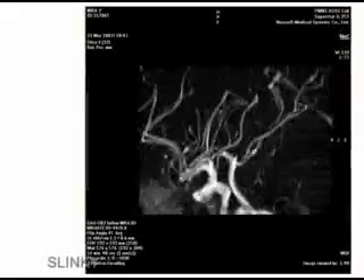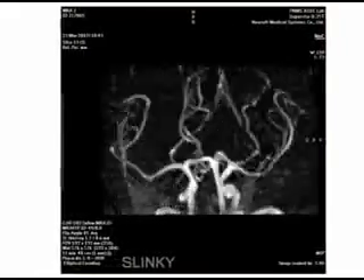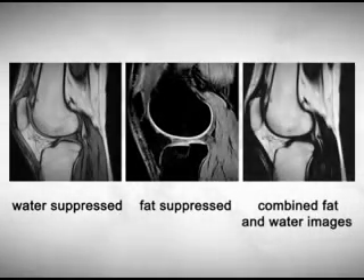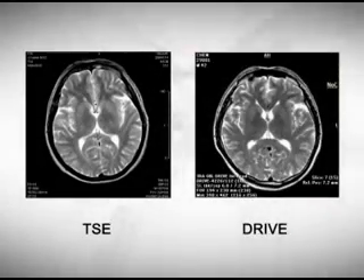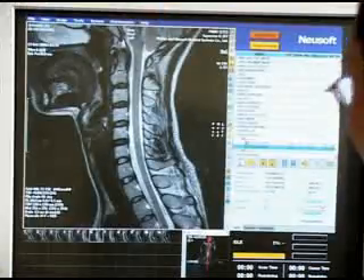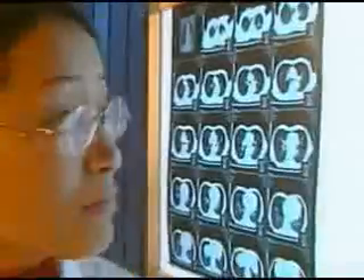The Superstar's acquisition method in MRA 3D is called Slinky, a technique that can improve the continuity of vessels. Through single scanning, water-fat separated imaging technology achieves three types of images. DRIVE can observably increase SNR especially in cerebrospinal and other body liquids. This sequence is useful for small apparatus imaging targets such as the inner ear, eye, and some brain details. The DRIVE sequence is also able to reduce the TR of a TSE scan, resulting in shortened scanning time.